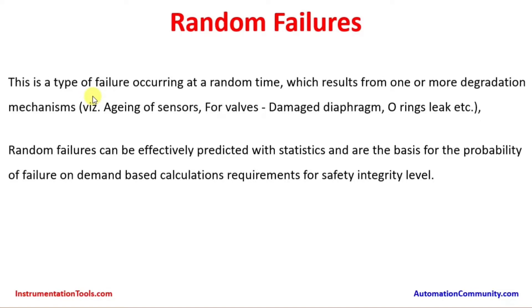Random failure is a type of failure occurring at a random time which results from one or more degradation mechanisms. For example, aging of sensors — this is applicable for SIS sensors. For valves, examples include damaged diaphragm, o-rings, leaks, etc. Valves have many mechanical components like seals, o-rings, and pneumatic devices, and any damage in those diaphragms can result in a random failure.